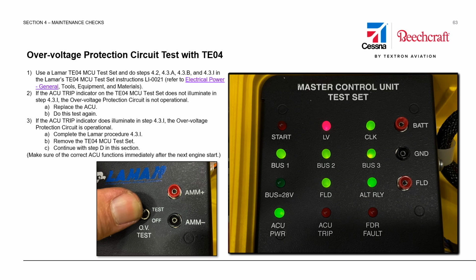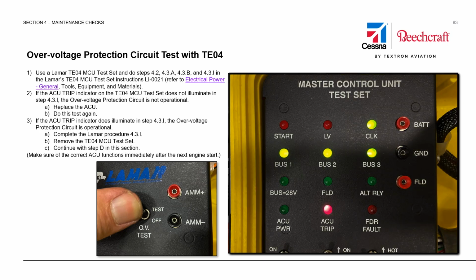As we proceed through the checklist, we come to the overvoltage test, where we will move the OV switch to the test position and hold for 5 seconds. We should observe the ACU trip light illuminate and the ACU power, field, and alt relay lamps should extinguish. Note that the alternator field circuit breaker should not open.